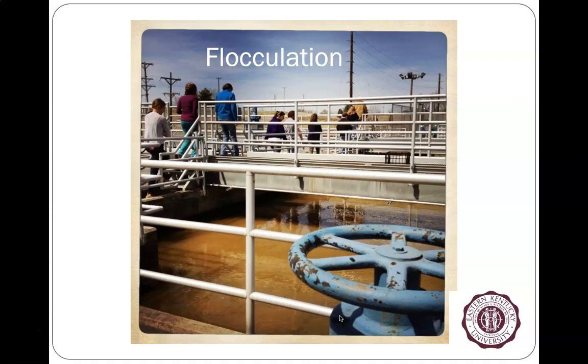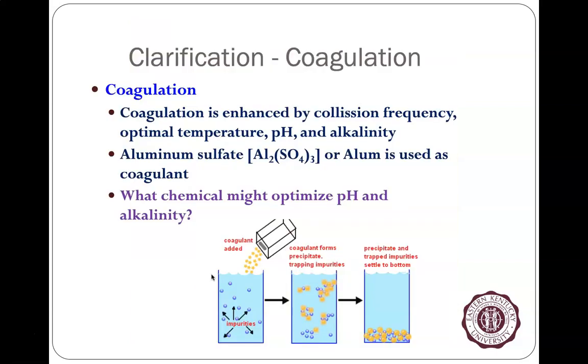At the Richmond water plant, after the chemicals are added and flocculation starts, you will actually see these little beads form in the water. You can look at them and see them. Not bubbles, but these little round globs. It'll be turbid or muddy water, but beyond it being just turbid or muddy, you'll see even bigger little chunks of things sinking. Coagulation is that process of adding the chemicals and doing the mixing.